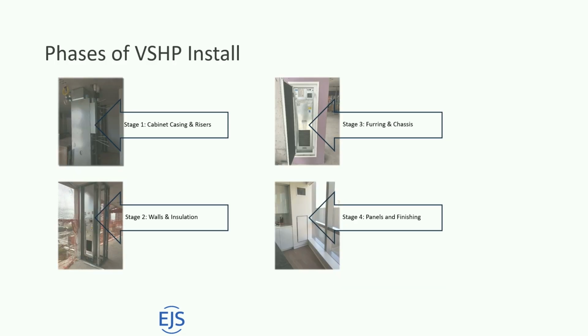It's kind of the phases of the install. When you're putting track down, we're putting cabinets on. Cabinets do need to be installed after skin's on the building so it's not exposed to the elements. Chassis aren't going in until typically we're ready for cooling and heating. There's your access panel on your bottom right there, your stage 4.